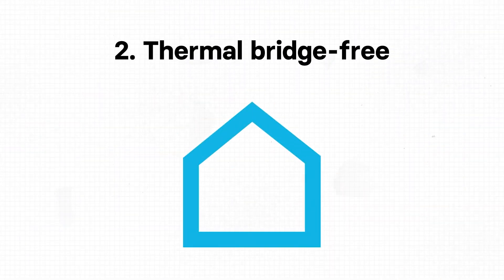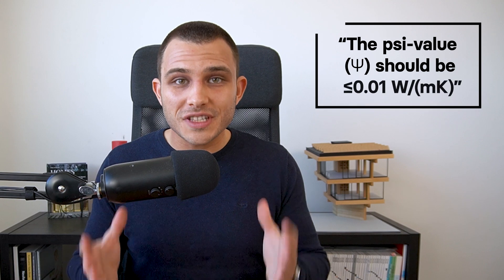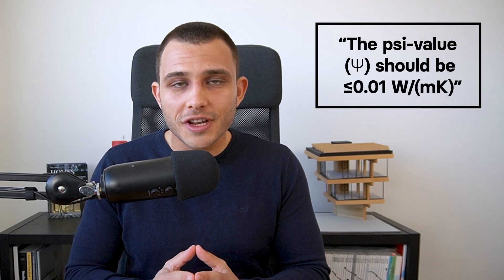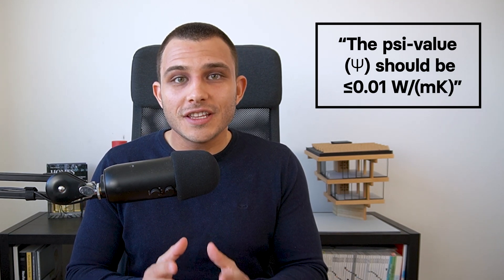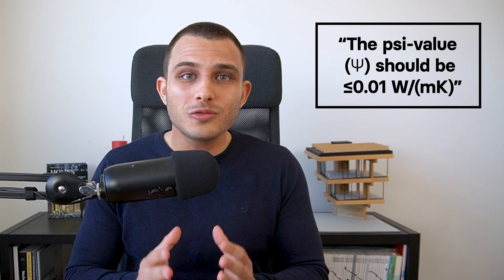The second principle is thermal bridge free design. Thermal bridges are the weak spots in our insulation layer — wherever the insulation layer is interrupted or another material goes through it, these details should be optimized. Thermal bridges are measured with the Psi value, and to have a thermal bridge free construction, this value should be less than or equal to 0.01 watts per meter kelvin.